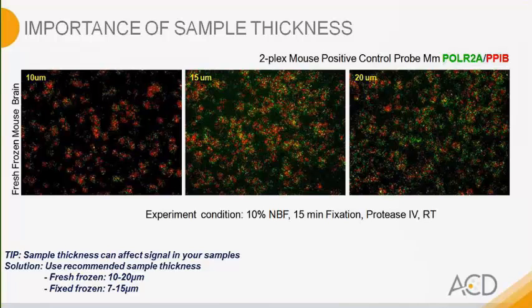For sample preparation, sample thickness is also very important for detecting signals. So this slide here shows that we have stained different thicknesses of fresh frozen mouse brain samples with our positive control Polr2A and PPIB control probes. As you can see here, the sample thickness varies, and the signal levels vary with the sample thickness; the thicker the sample, the more signal you get. So this data suggests that the sample thickness can also affect signals in your sample.